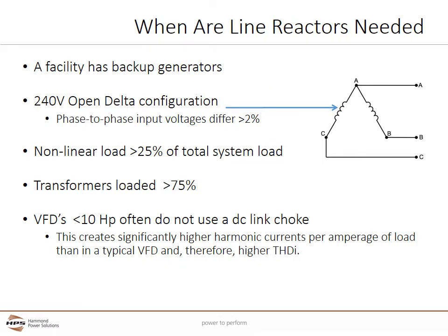Line Reactors should be considered if a facility has backup generators to aid in proper operation and minimum sizing. 240-volt open delta configurations can benefit from additional impedance. If the phase-to-phase input voltages differ more than 2%, consider adding line reactors. If the non-linear load is more than 25% of the total system load, at a minimum line reactors should be added.